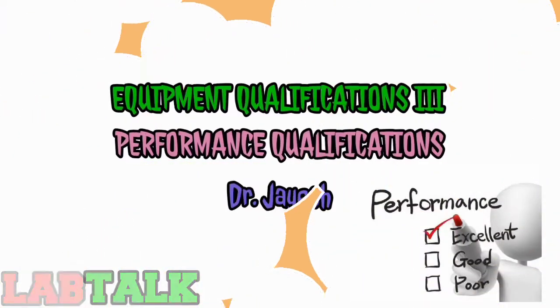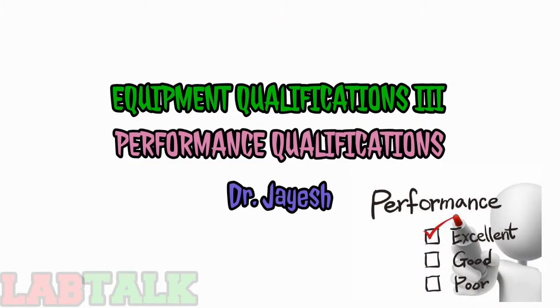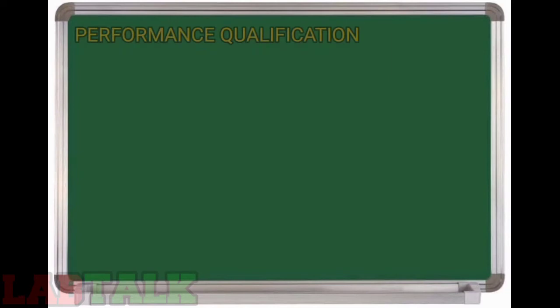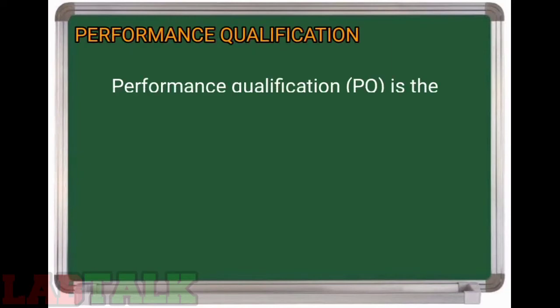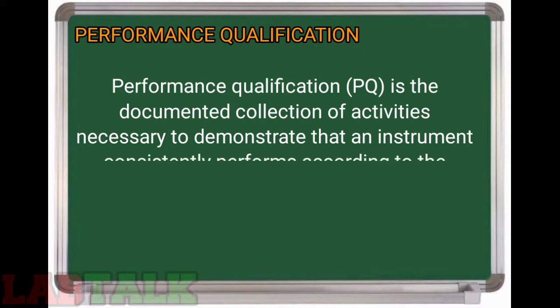Hey friends, welcome to Lab Talk. I am back with the third video in the series on equipment qualification. The next part in the equipment qualification is Performance Qualification. Performance Qualification or PQ is the documented collection of activities necessary to demonstrate that an instrument consistently performs according to the specifications defined by the users and is appropriate for the intended use.